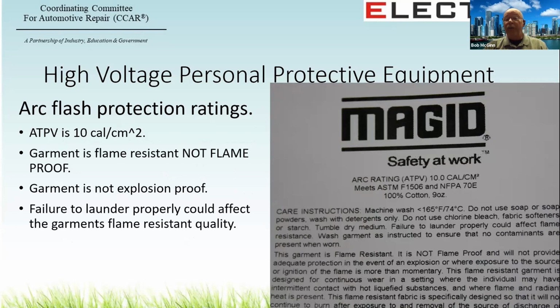The inner tag lays out the details. Arc thermal protection value, 10 calories a square centimeter. The garment is flame resistant and not flame proof. And I love that they put it, but they have to put it in the tag. But is there anybody out there that seriously thinks that this cotton jacket would be flame proof? Along with the fact that the garment is not explosion proof. But washing it incorrectly may be a problem, because if you wash it, dry it, add any fabric softener or anything that they tell you not to do, according to that label, it will reduce the arc thermal protection value of the garment. So please be careful with how they are laundered if you are using them.